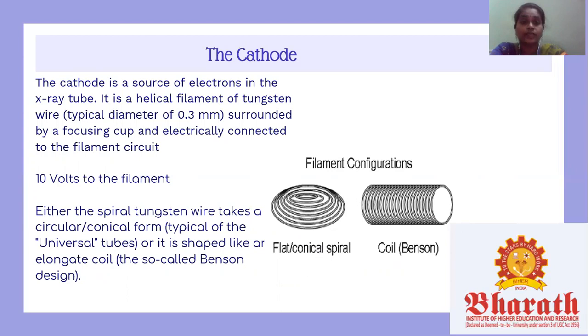The filament is located in a cylindrical chamber or slot in the cathode. As a rule, the focal spot is similar in size and shape to the opening. The size and shape of the focal spot is partly determined by the filament's position relative to other components of the cathode. The focal spot size can be reduced by positioning the filament deeper in the slot in the cathode, or increased by moving the filament closer to the top of the opening.